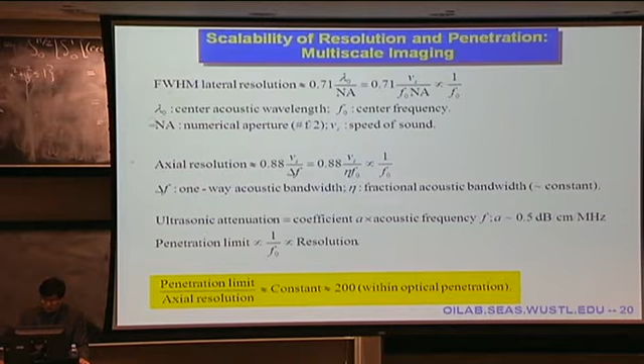So what we're looking at is the scalability afforded by ultrasound. And we're scaling to a clinical ultrasound machine here. This is an ultrasound machine made by Philips, and this is a joint project with Philips. We've adapted a standard clinical ultrasound probe. It's a linear probe for photoacoustic imaging without giving up on the ultrasound imaging capability. So this is for simultaneous ultrasound and photoacoustic tomography.